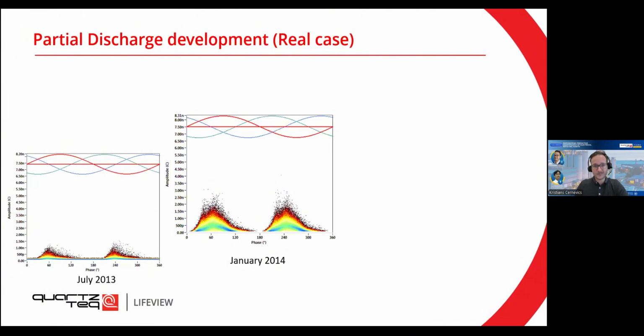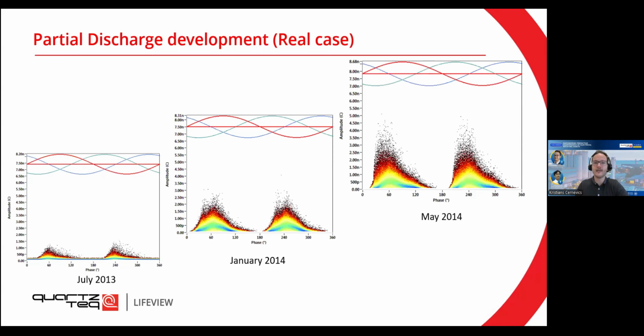So what was then decided in January is that the next measurement would be made a bit earlier. It was made at the beginning of May, and what they saw again was almost a double increase. At this point, Quartzteq suggested the motor be stopped before catastrophic failure, because we had reached the point where the partial discharges grow very, very fast. It means that the machine health is deteriorating very fast. This was a type of measurement that helped us predict that the machine needed to be switched off and repaired.